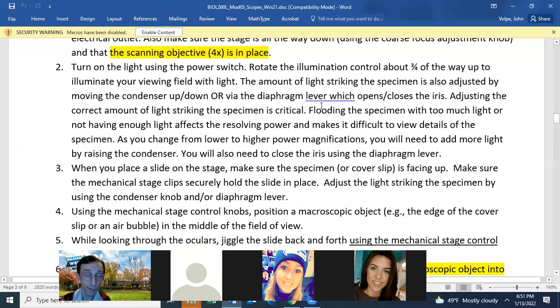When you're first using the microscope, open up the iris diaphragm so the cone of light is equal to the field of view. The cone of light will open up everything you can see under the microscope. So you have the iris diaphragm open as large as you can with the 4X lens. Set the lamp to what's easy to view, meaning you don't have it so bright it's hard to view, and not so dim it's also hard to view.